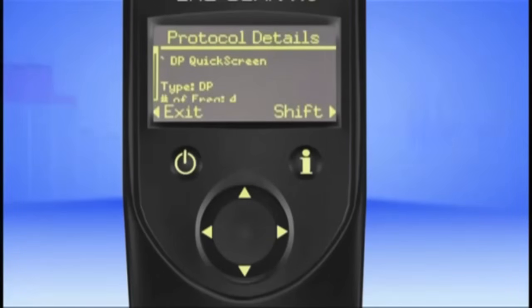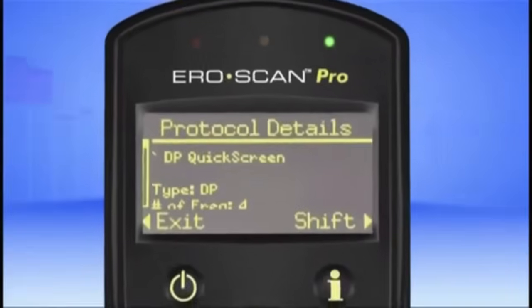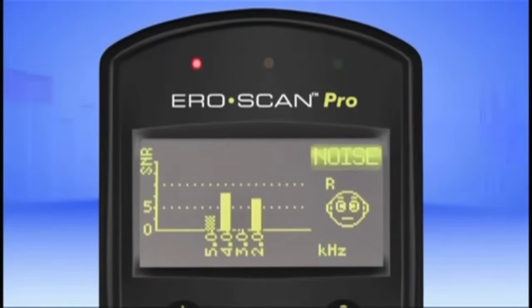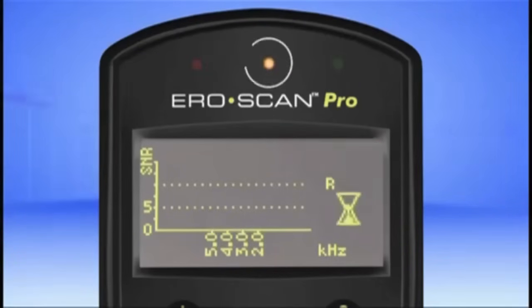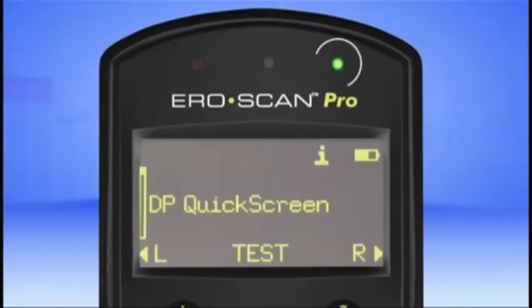Finally, located at the top of the control panel are the test status indicators. These 3 indicators alert you to the status and various operating conditions of the Ero Scan Pro. The red status light means that one of the following conditions has occurred. There was a noise present during a test, good ear tip seal was not maintained, or that an error condition exists. The amber status light indicates that a test is currently in progress. The green status light means that the unit is on and ready to test.